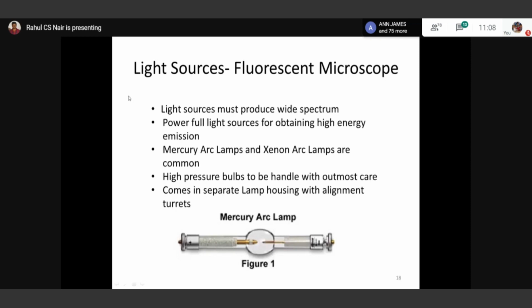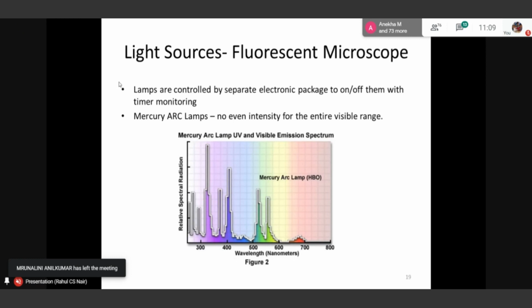Other than mercury, there is also the xenon arc lamp, and you can see the mercury arc lamp spectrum here. It covers almost the visible light range from 400 to 700 nanometers. Intermediately, some wavelengths are missing, and that is the main disadvantage of mercury. Usually these mercury lamps are operated with a timer because they have a 200-hour lifetime, so we need to know how much time has expired. The power pack usually comes with a timer built in, and it gives you intensity from all over the visible spectrum.